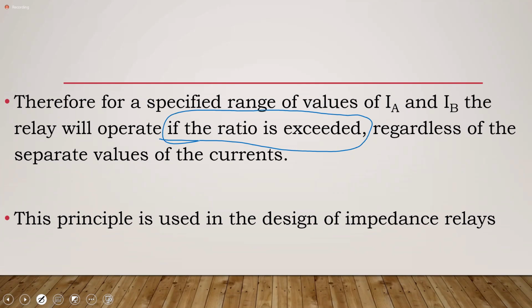Once it changes, because normally, when you have a fault, the current is much larger than the voltage. So the increase in current will be much larger than the voltage. As a matter of fact, the current will increase, and in most instances, the voltage will be lowered. So what you'll have is that the impedance would then be smaller than the preset value. So the impedance relay operates on the principle that once the impedance falls below a preset value, it should operate. All right.